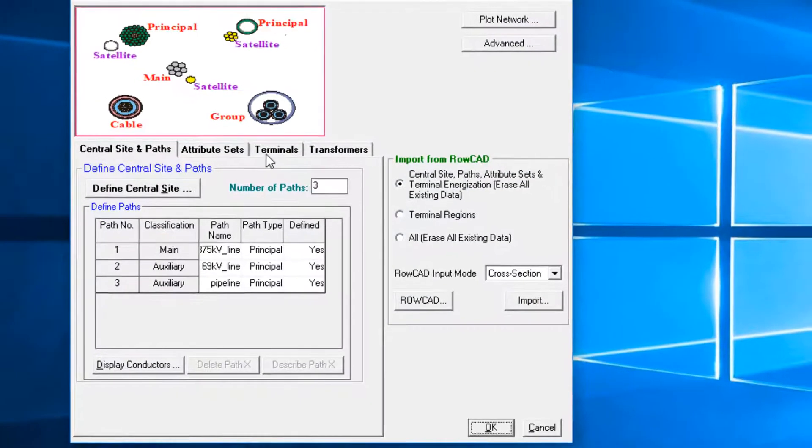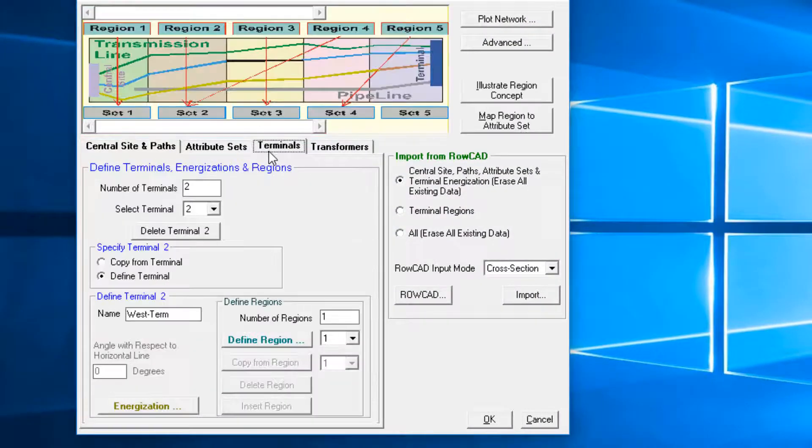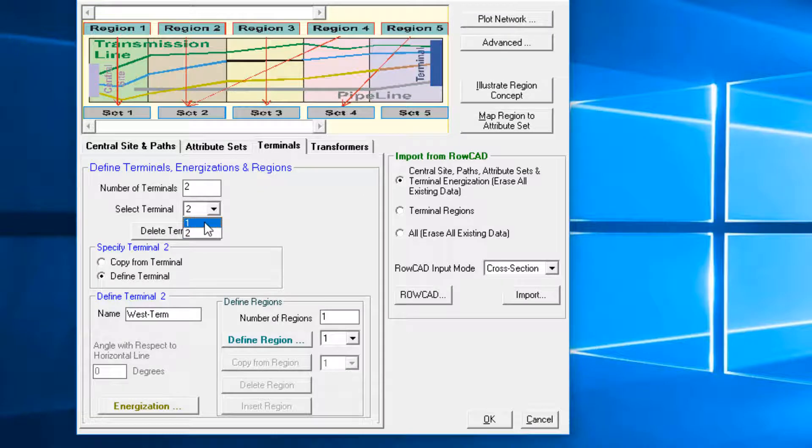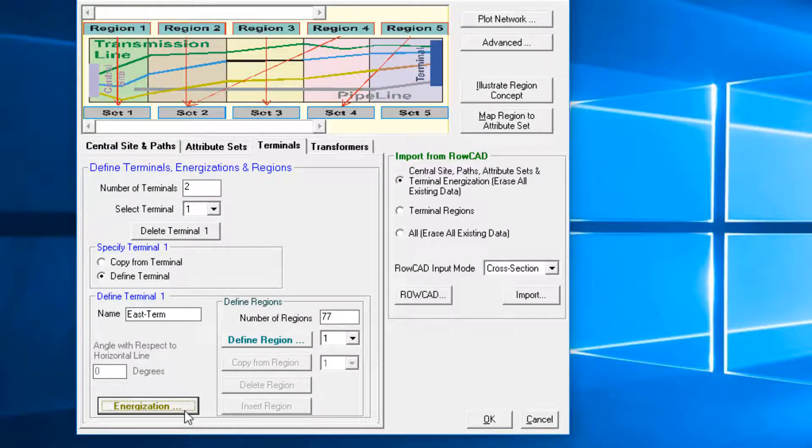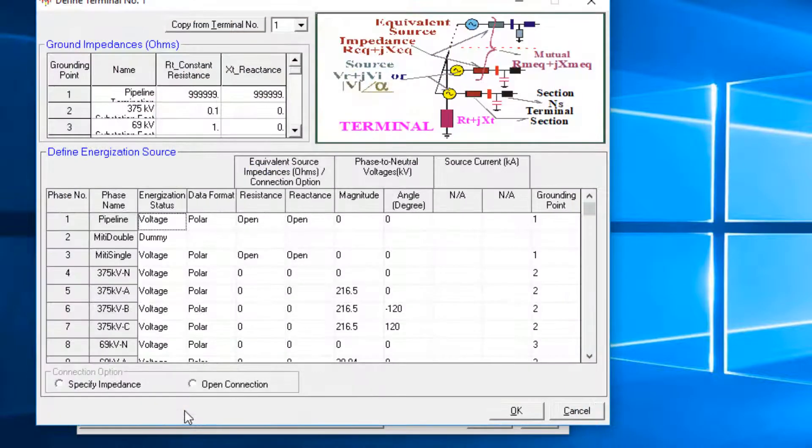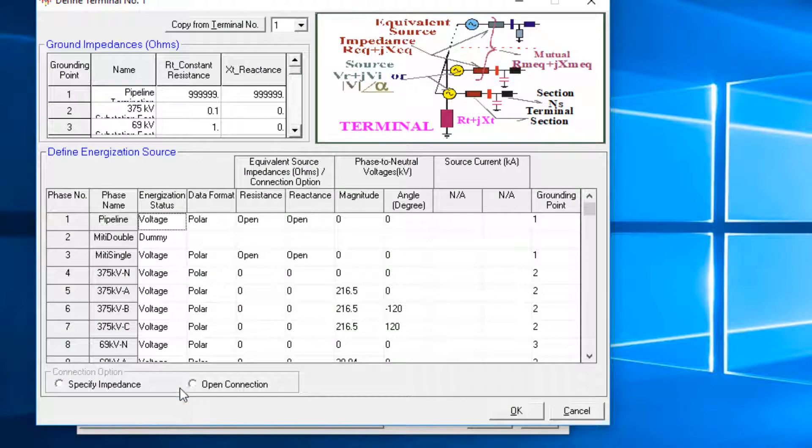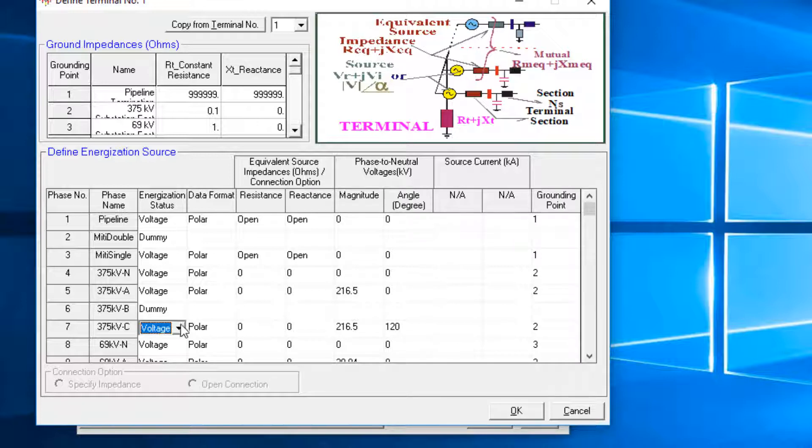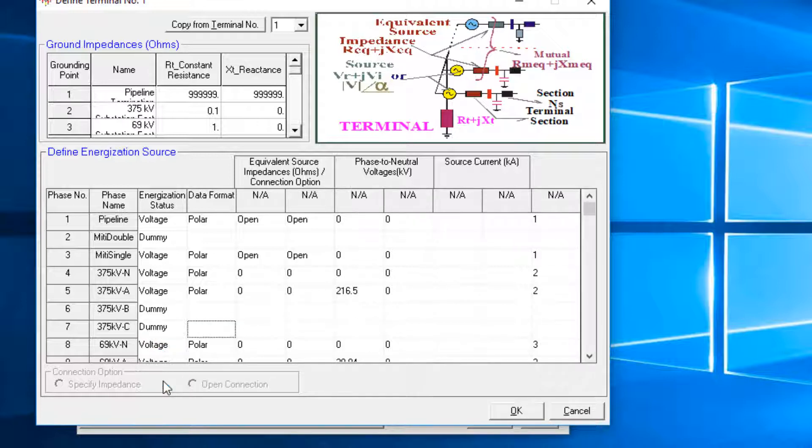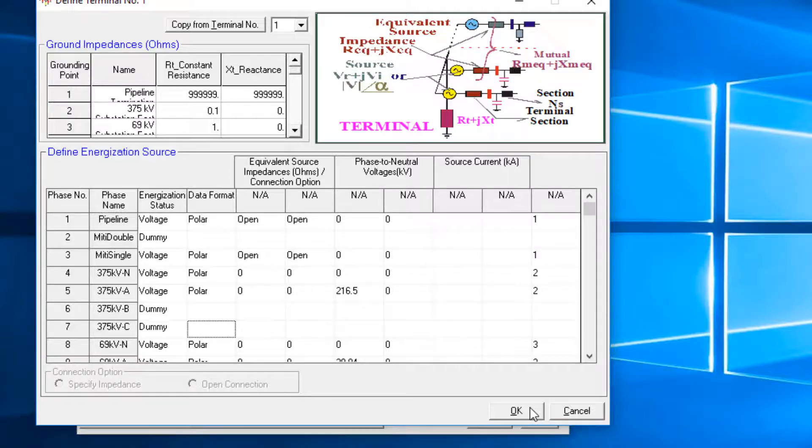Choose Terminal 1, then click on Energization, and modify the energizations so that Phase 6 and 7, which are 375 kV B and C are set to Dummy. Here we choose Phase 5 as Faulted Phase, because it's closer to the pipe along most of the corridor. Repeat the same for the second terminal.